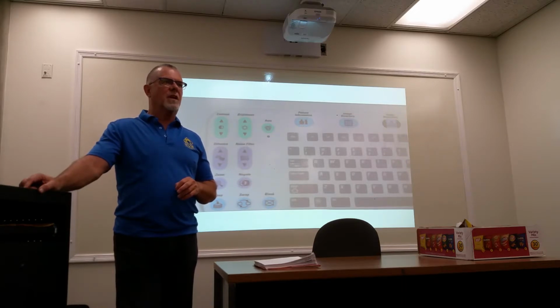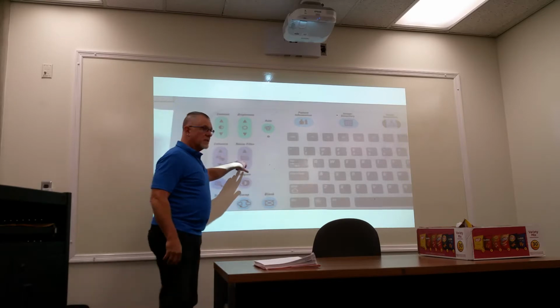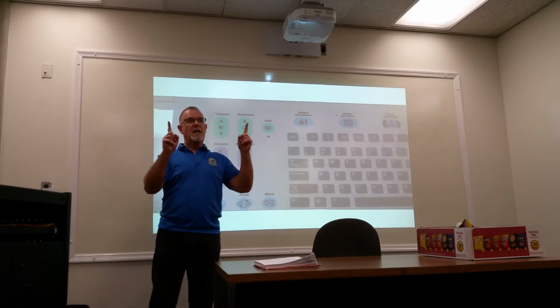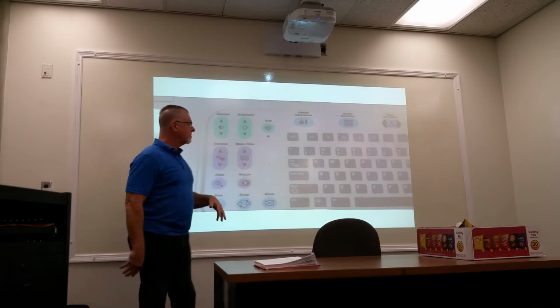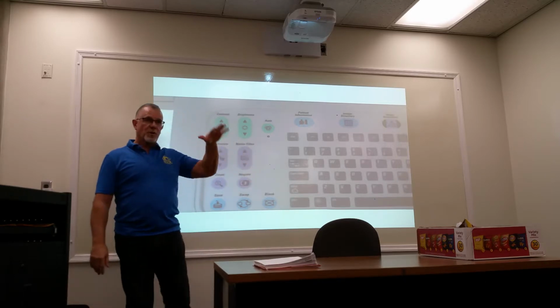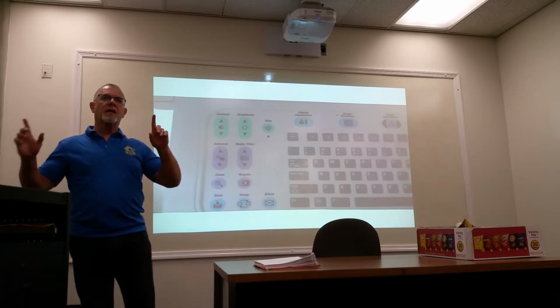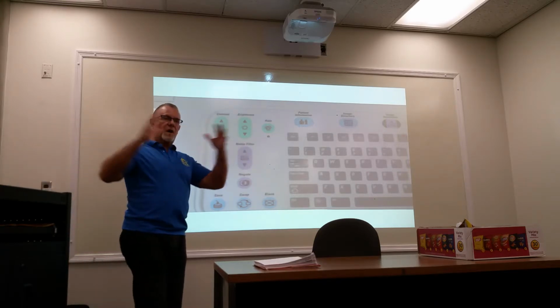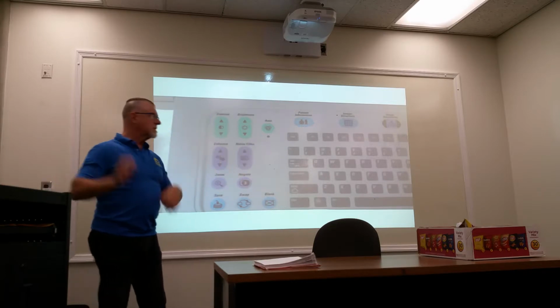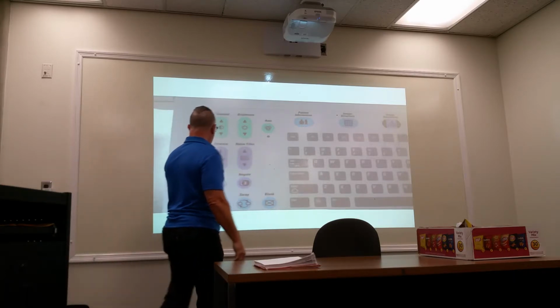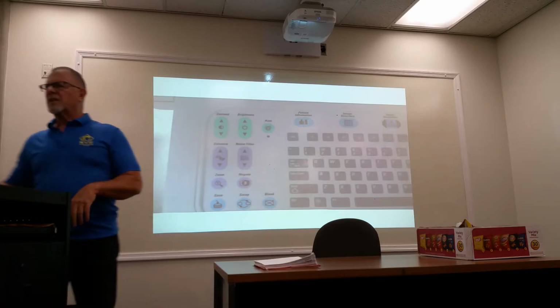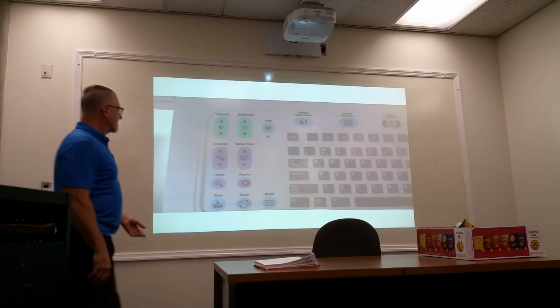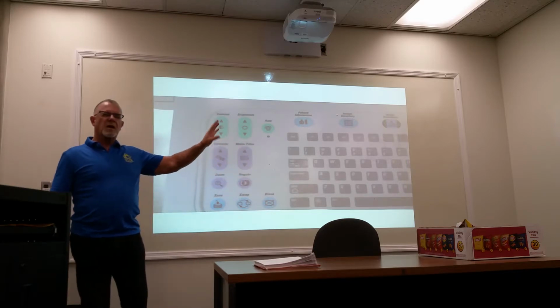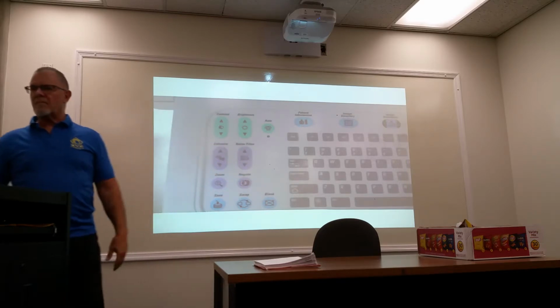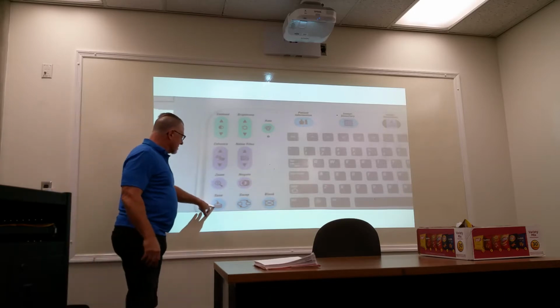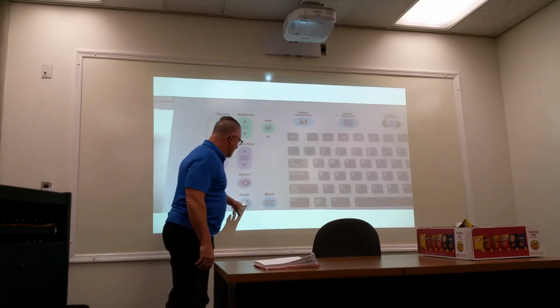Frame averaging. So this is going to get rid of the noise; it's going to determine how many of those pulsed shots are going to be added together to bring the noise down. Okay? As you bring the noise down, you get more image lag because it takes longer. You've got more frames being added together before you add the next set. But that allows you to change your noise. You've got some zoom. You've got some negative. So that allows you to go from white on black to black on white. Again, a typical thing for saving, swapping monitors.